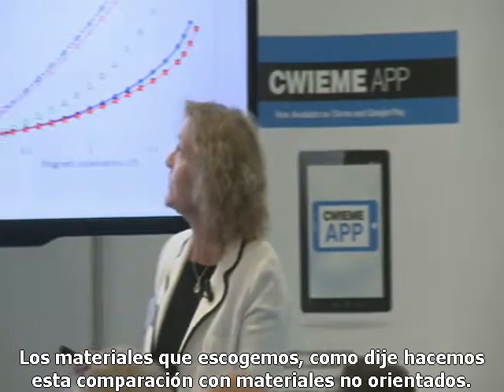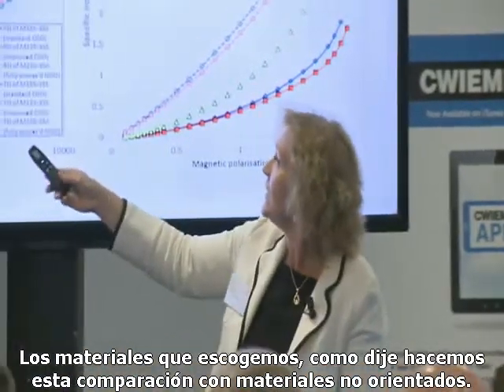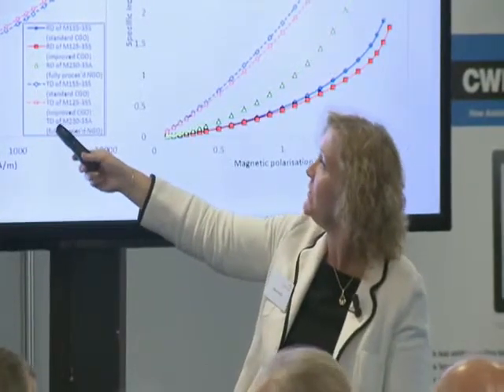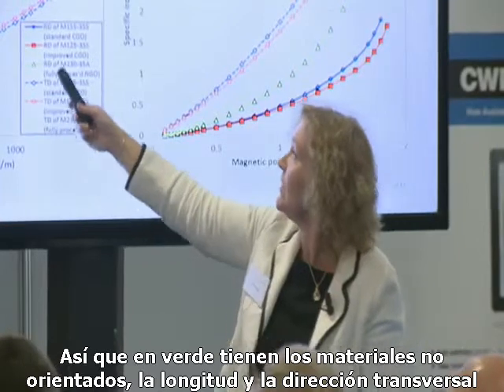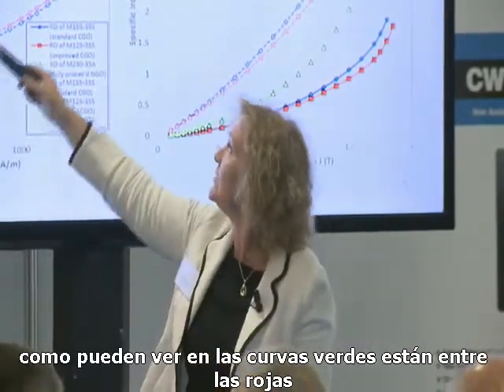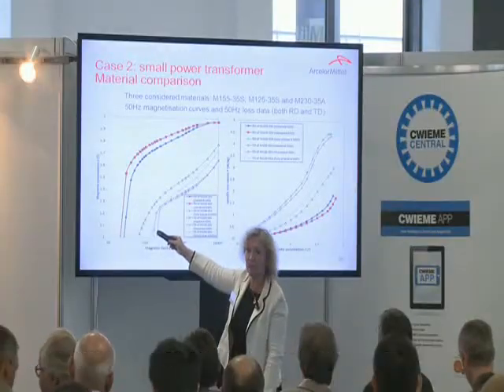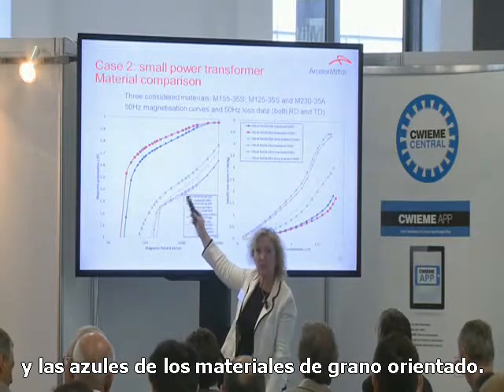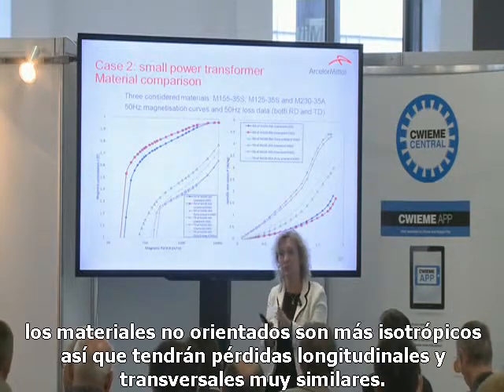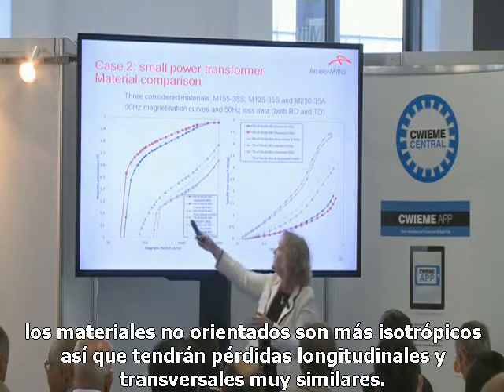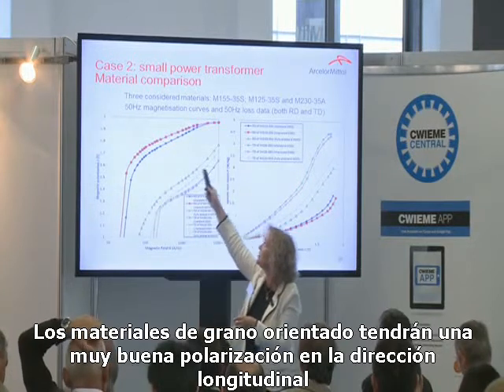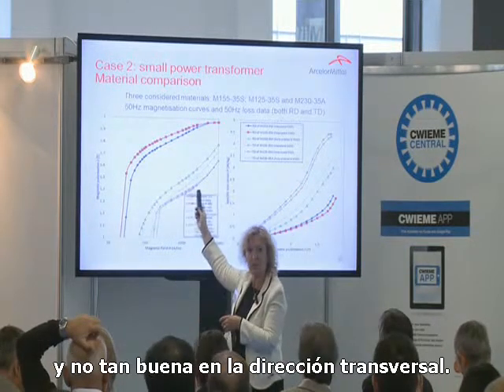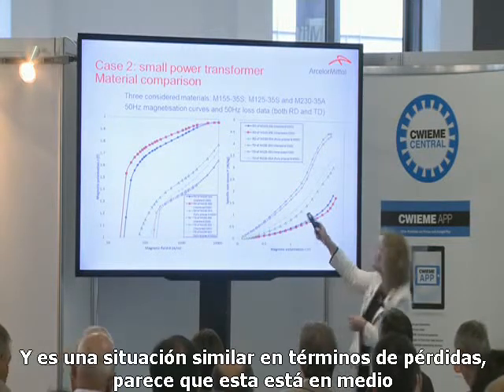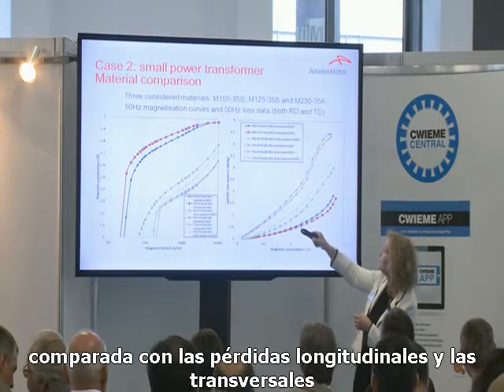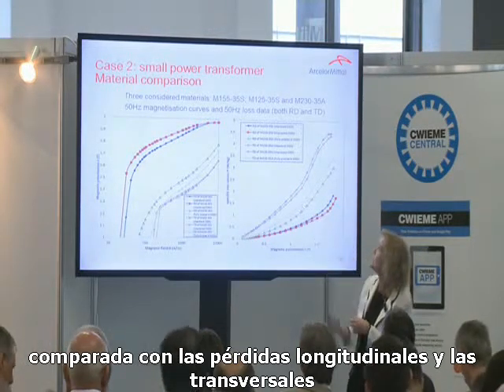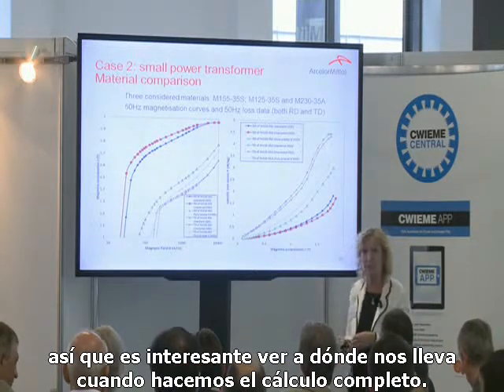The materials we chose: we made a comparison with non-oriented material. In green you have the non-oriented material, longitudinal and transverse direction. You can see the green curves are in between the red and the blue of the grain-oriented materials. The non-oriented material is more isotropic, so losses longitudinally and transversely are quite equal. The grain-oriented material has a very good polarization in the longitudinal direction and not such a good polarization in the transverse direction, and it's a similar situation in terms of losses. It looks like this one is in between compared to the longitudinal and transverse losses. So it's interesting to see where it brings us when we make the full calculation.